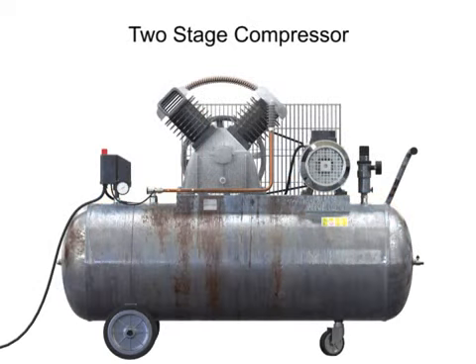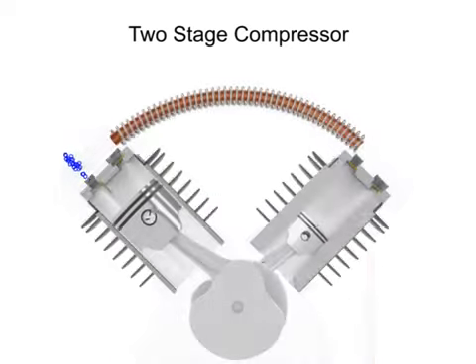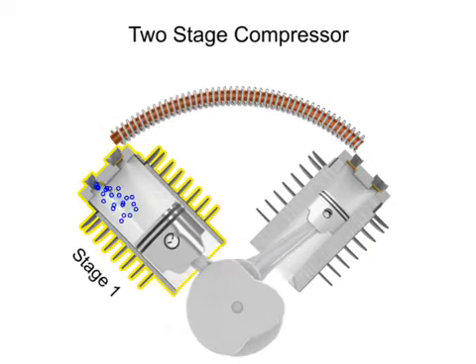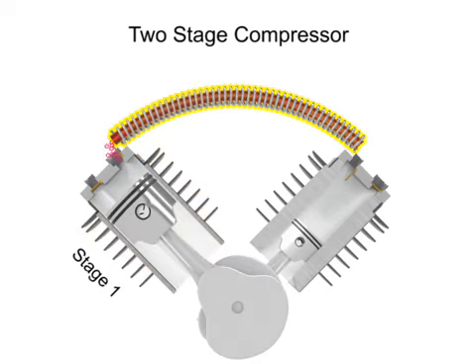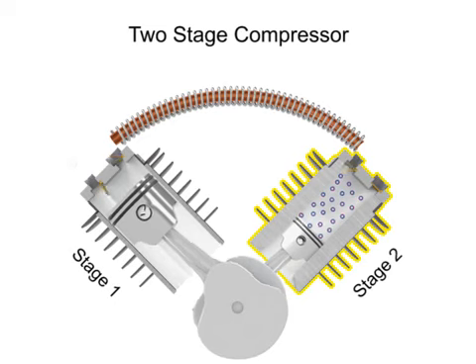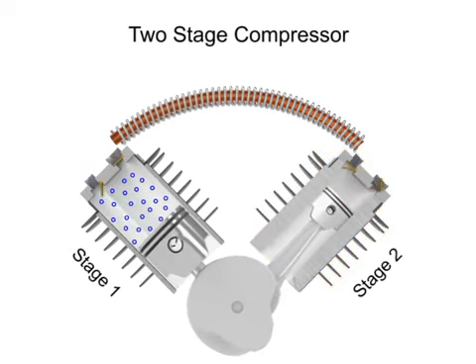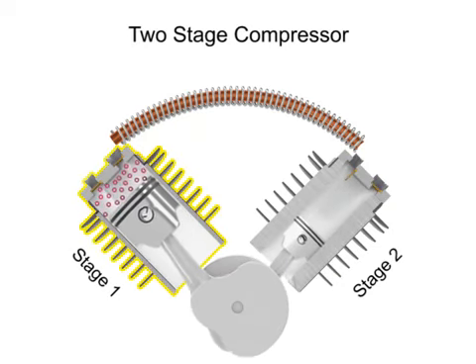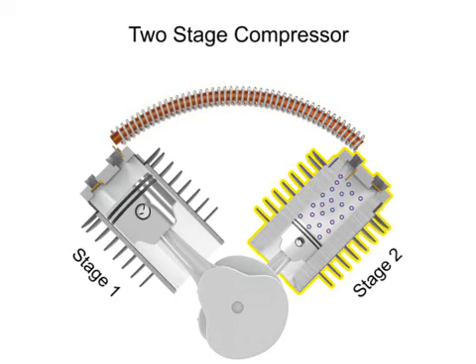To avoid the hazards of overheating and still generate higher pressures, manufacturers make compressors with multiple stages. The air is compressed in the first stage, which is typically the largest stage, then cooled, then compressed in a second stage. The hot compressed air from the first stage is conducted to the second stage through finned tubing exposed to air from a flywheel fan. After the air is cooled within the tube, the compressed air enters the second stage to be compressed even further.